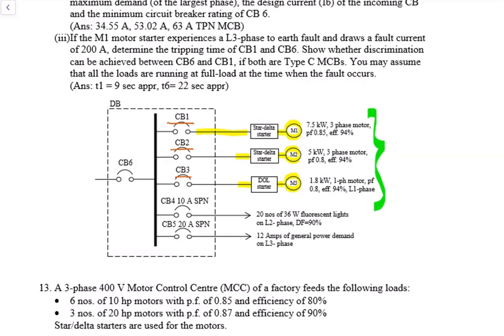So the power formula is I full load equals power over the voltage multiplied by power factor multiplied by efficiency. Just remember that the voltage to use depends on whether it's 3-phase or single phase. If it's 3-phase, we use √3 times 400 volt, or if it's single phase, we use 230 volt.